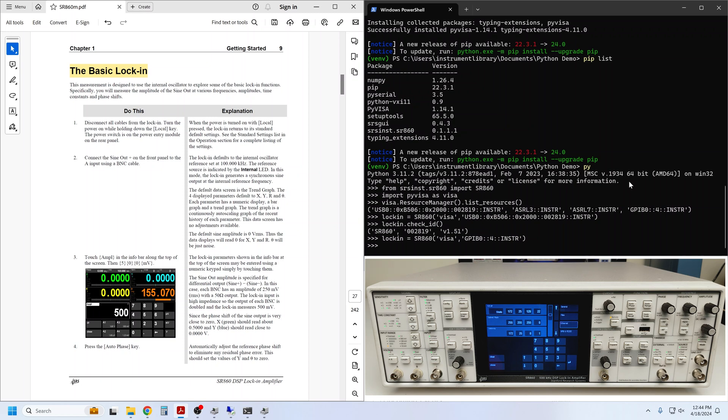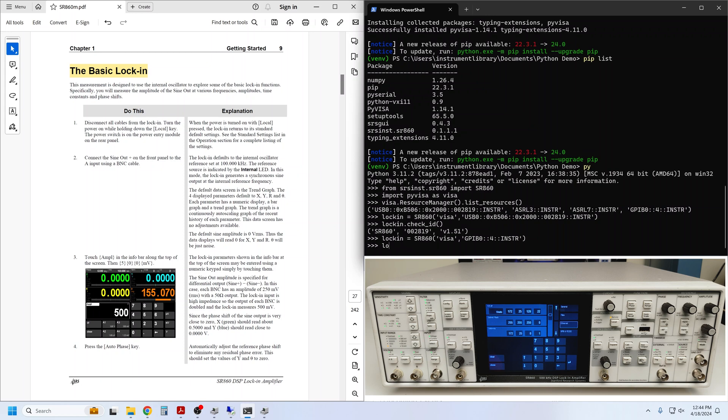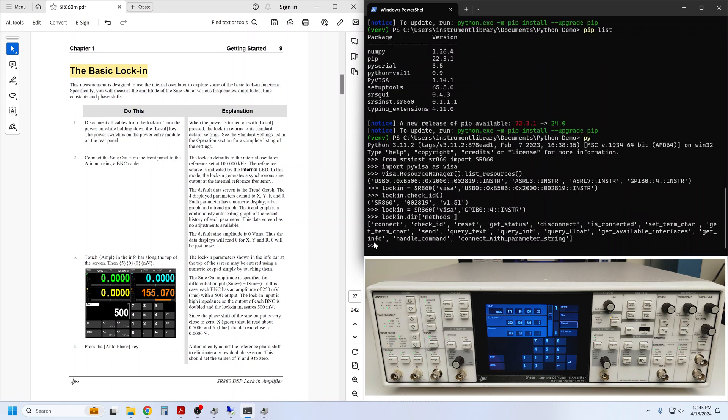In the Python prompt, we have already imported the SR860 driver and established a connection via your preferred interface. The guide instructs us to turn on the instrument with the local key. This simply restores the lock-in's default settings and is equivalent to sending the reset command. If you recall from last time, we learned about the DIR helper and one of the methods available at the top level is reset. So I can simply call lockin.reset.